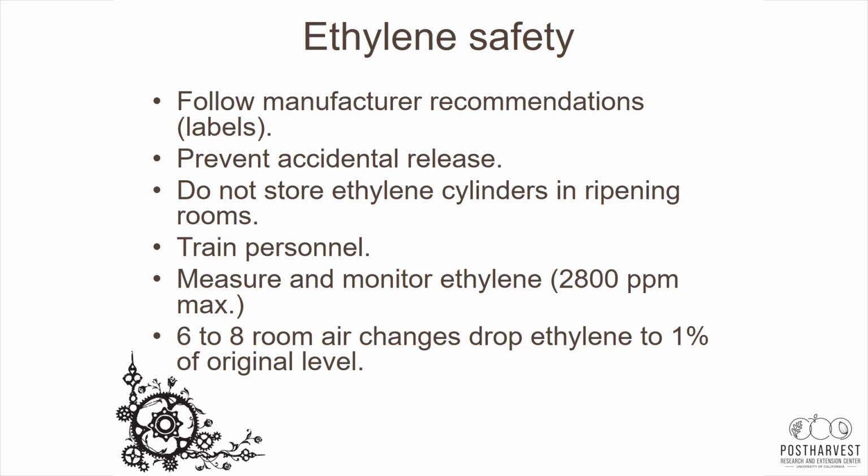Again, measure and monitor ethylene above this level, but ethylene is combustible at extremely high concentrations, around 28,000 parts per million. So it's even much higher than the recommendation that we have here. But it's just a kind of safety concern. Keep your eyes open.